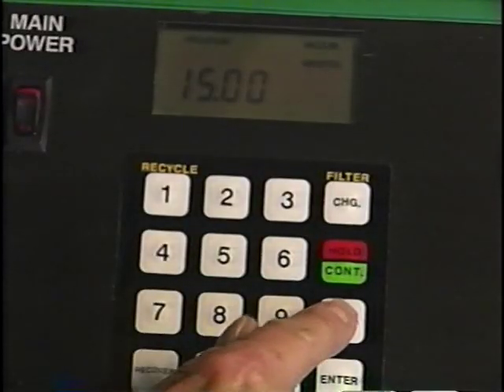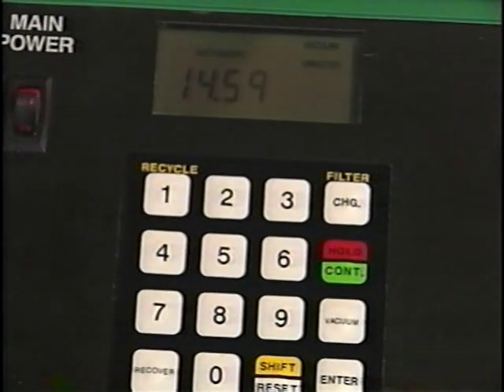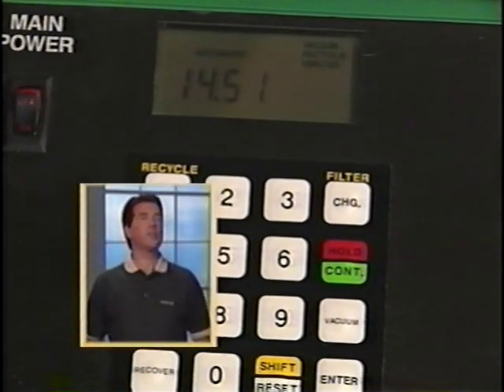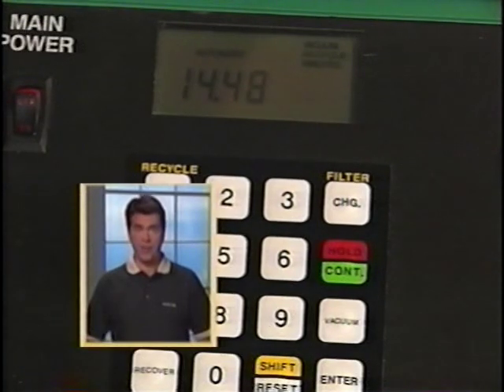Press the vacuum key on the panel to start the vacuum pump. A predetermined time of 15 minutes will show on the panel. We can get a longer time than 15 minutes if desired. Never shortcut the 15-minute vacuum process. If you recover sooner, chances are you're going to put air in the car.